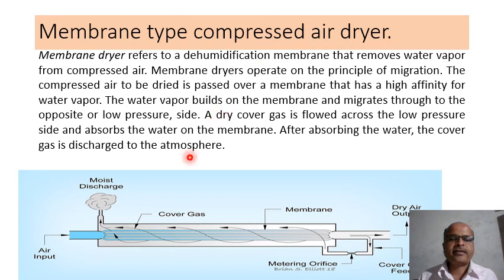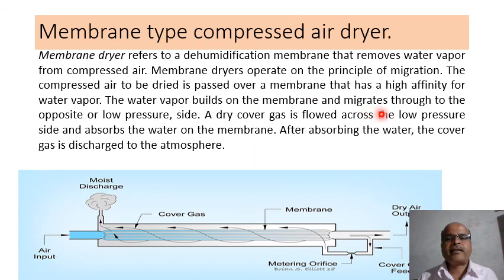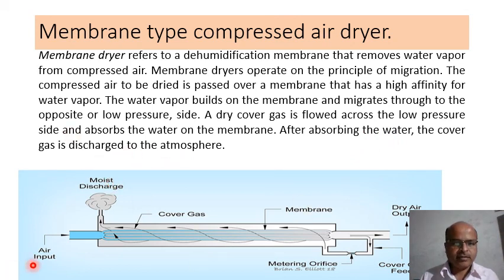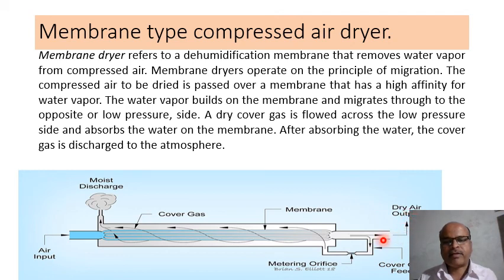Membrane type compressed air dryer: The membrane type refers to a dehumidification membrane that removes water vapor from compressed air. Membrane type dryers operate on the principle of migration. The compressed air to be dried is passed over a membrane that has a high affinity for water vapor; the water vapor builds on the membrane and migrates through to the opposite lower-pressure side. A dry cover gas flows across the low-pressure side, absorbs the water on the membrane, and is then discharged to the atmosphere. The diagram shows: air input, moist discharge, cover gas, membrane, and dry air output.